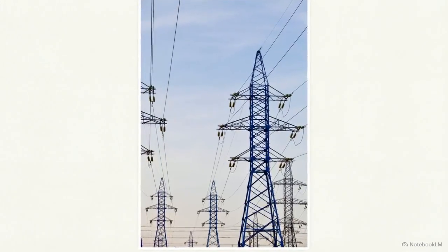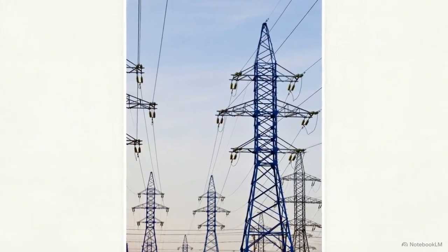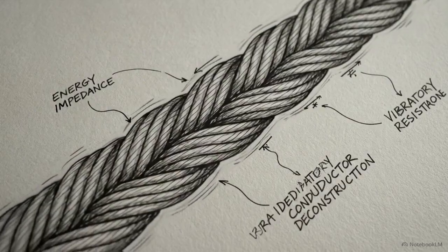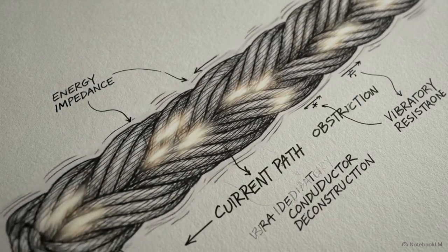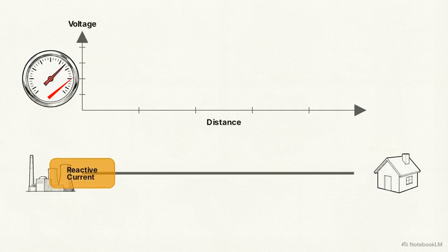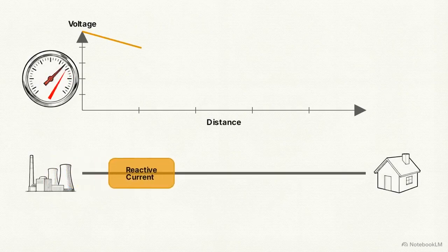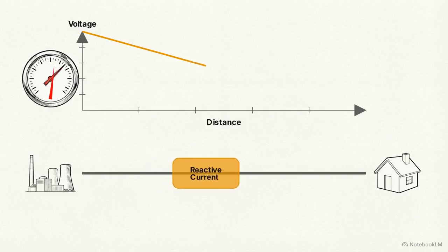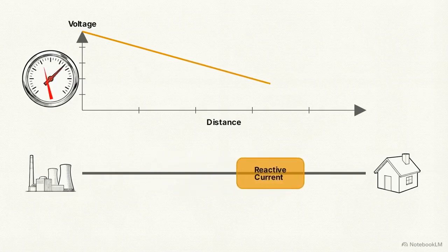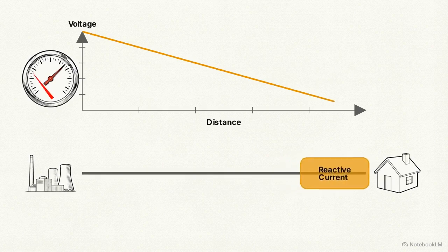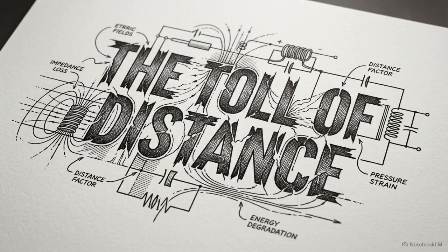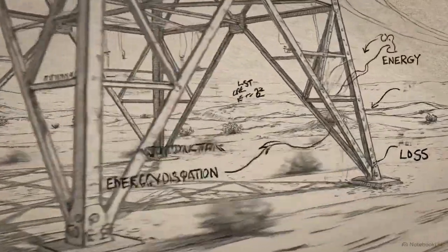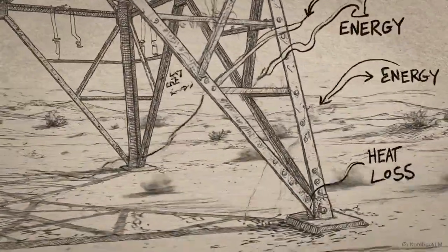The farther this high reactive current has to travel, the more friction it encounters. As it pushes across hundreds of miles of high voltage lines, it constantly fights the natural electrical resistance of the wires themselves. Forcing that extra current through the wire causes the voltage pressure to drop. Mathematically, the longer the line and the higher the reactive current, the more severe that voltage drop becomes by the time it reaches its destination. This makes reactive power a terrible traveler. The very act of moving it across long distances actively destroys the voltage pressure you need to keep the grid running.